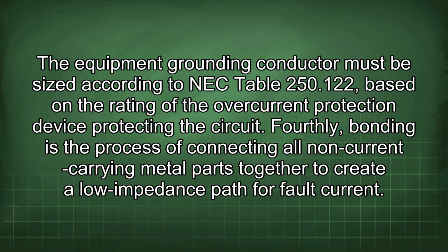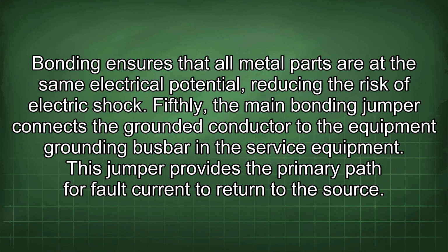Fourthly, bonding is the process of connecting all non-current carrying metal parts together to create a low impedance path for fault current. Bonding ensures that all metal parts are at the same electrical potential, reducing the risk of electric shock. Fifthly, the main bonding jumper connects the grounded conductor to the equipment grounding busbar in the service equipment. This jumper provides the primary path for fault current to return to the source.